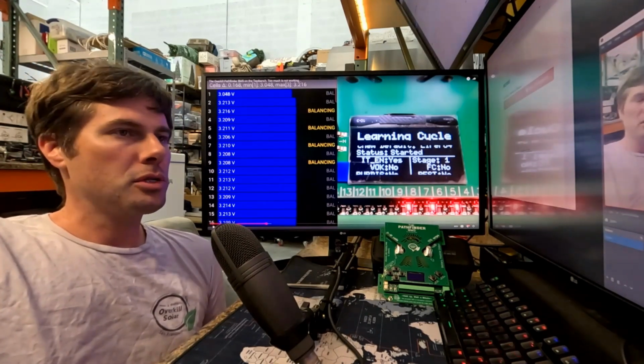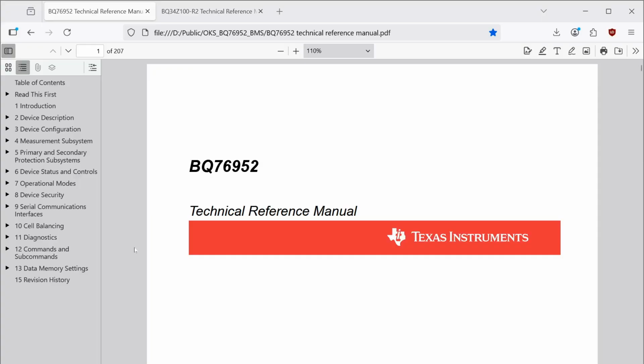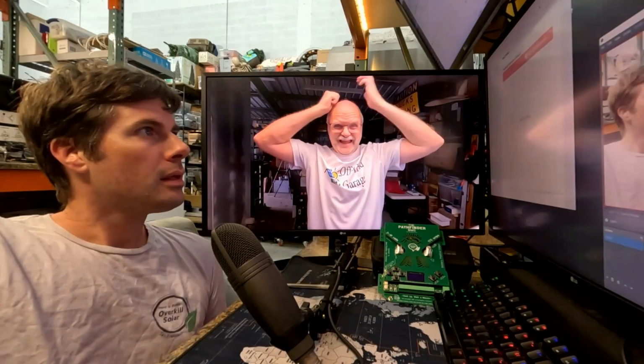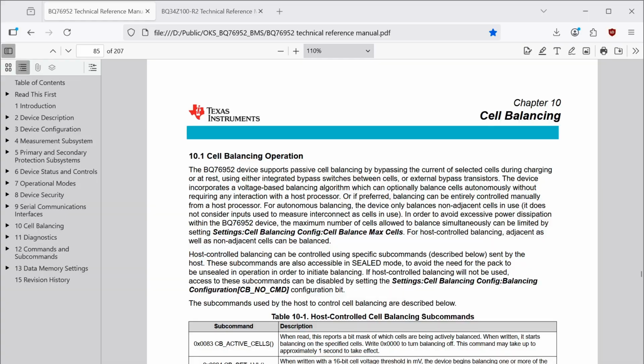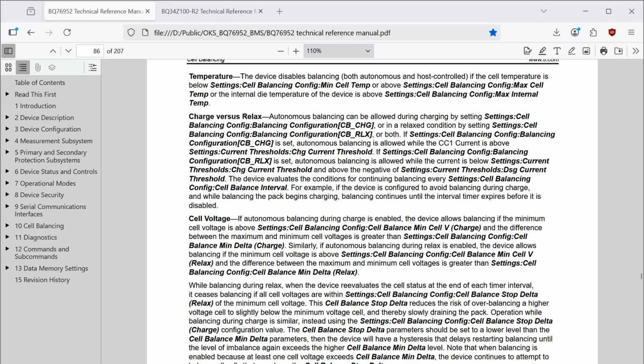All the balancer functions are controlled by this chip, the BQ76952 by Texas Instruments. If autonomous balancing is enabled, the device allows balancing if the minimum cell voltage is above cell balance minimum volts, and that's the setting Andy is setting there on the Pathfinder BMS, and the difference is greater than the delta.